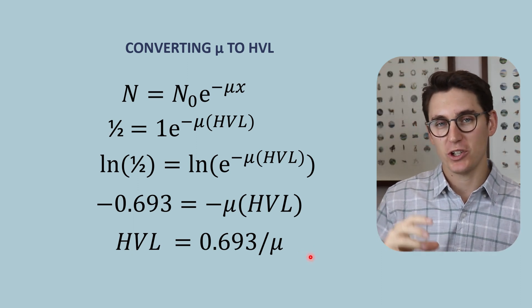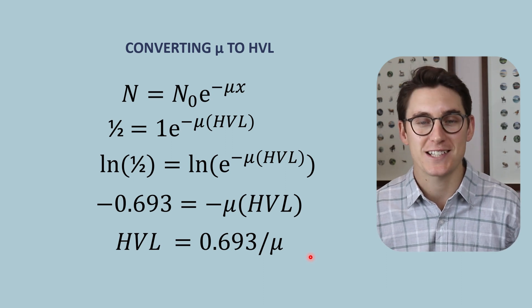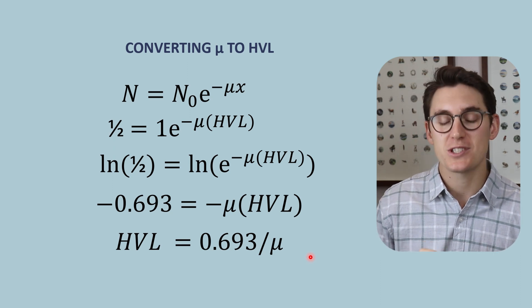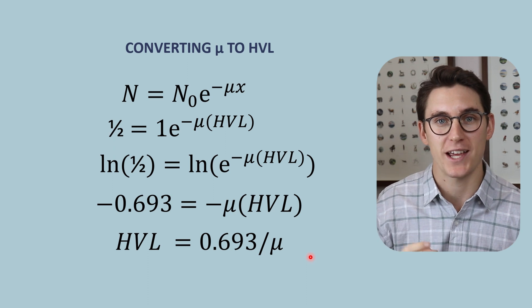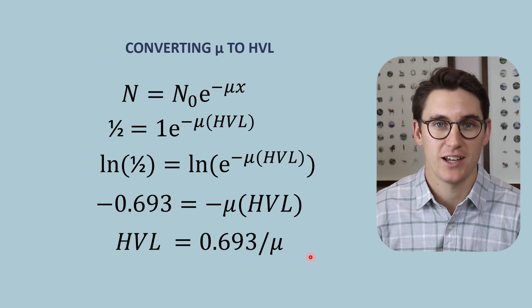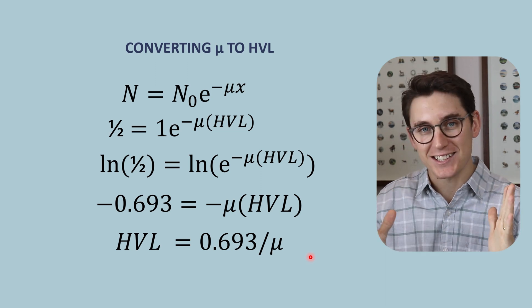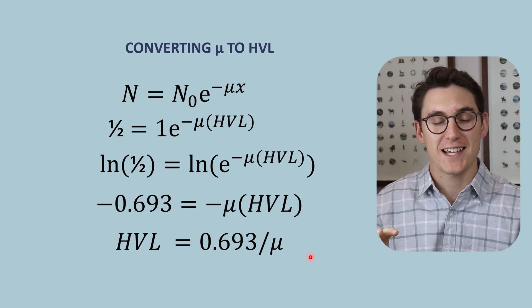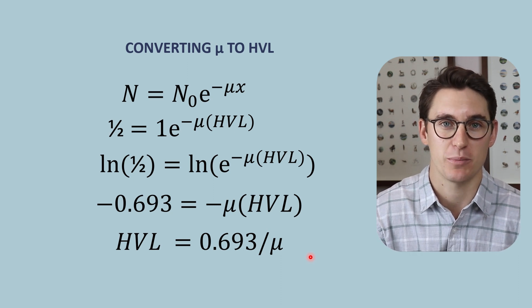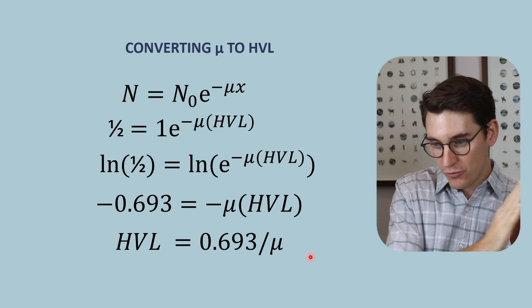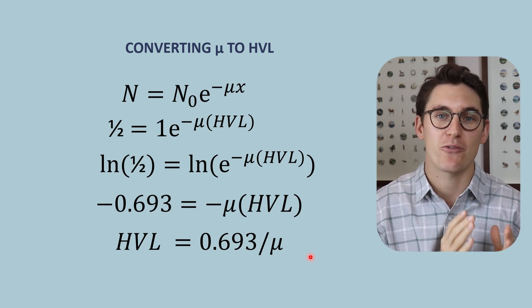So what have we actually calculated? We can use the linear attenuation coefficient as a good proxy for how specific tissues remove x-rays from a beam — bone, being more dense than water, removes proportionally more x-rays. The half value layer is a distance: how far x-rays must travel for their intensity to be halved. We can use the half value layer as a proxy for x-ray beam quality — the average energy of the beam. The higher the average energy, the further x-rays travel before intensity is halved, so as HVL increases, so does beam quality.